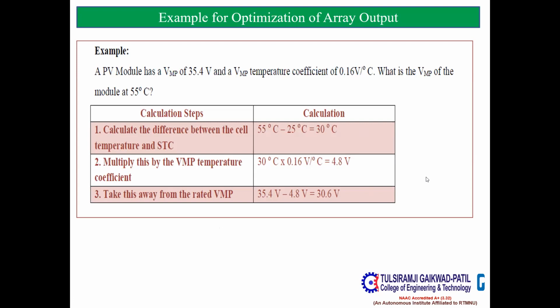This is a very important calculation, because most of the time we are under the impression that in the summer season we will get the maximum output from the solar PV system. But this is not the case. In summer season, the temperature coefficient effect is at its maximum, and because of that we need to size our system accordingly, so that it is neither oversized nor undersized. This part is very important. With the irradiance, if the temperature is also increasing, there would naturally be an impact on the VOC, that is, the open circuit voltage of the PV modules. So shall we proceed ahead?